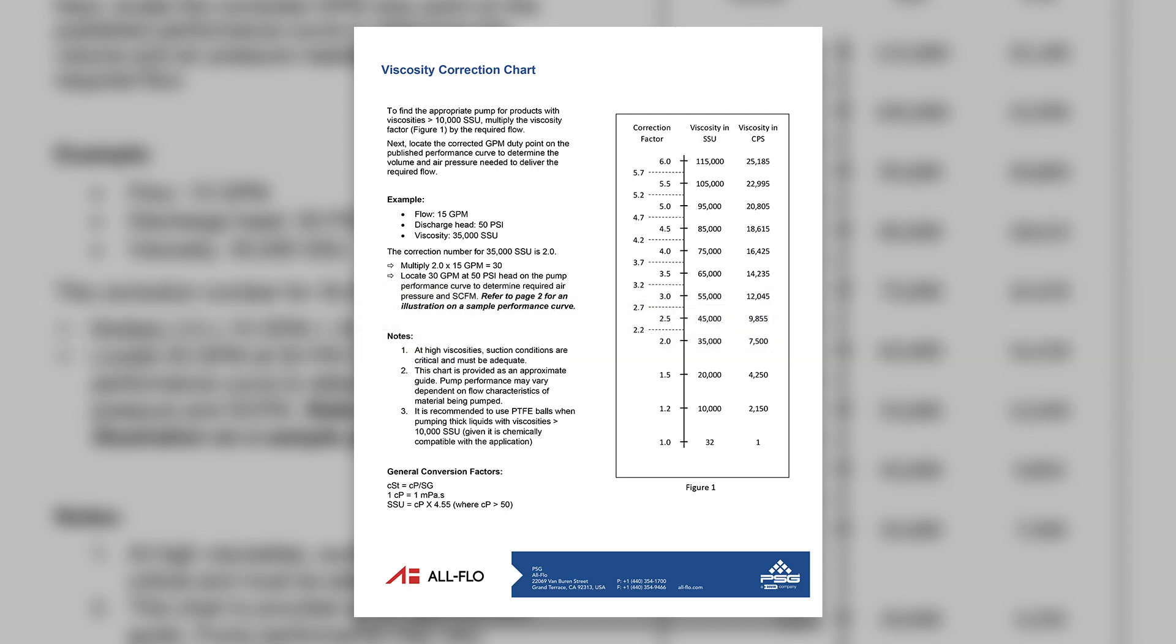As an example, let's say a manufacturing company is pumping a product that has a viscosity of 7500 centipoise at 50 PSI. Utilizing the All-Flo viscosity correction chart, identify the viscosity correction factor. In this instance, the viscosity correction factor for 7500 centipoise is 2.0.